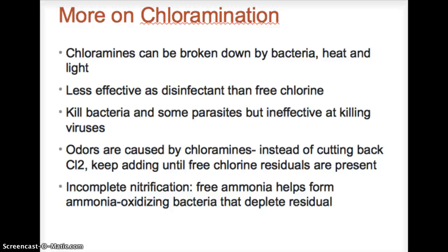Chloramines can be broken down by bacteria, heat, and light. They are less effective as a disinfectant than free chlorine. They kill bacteria and some parasites, but they are ineffective at killing viruses. Odors can be caused also by chloramines.